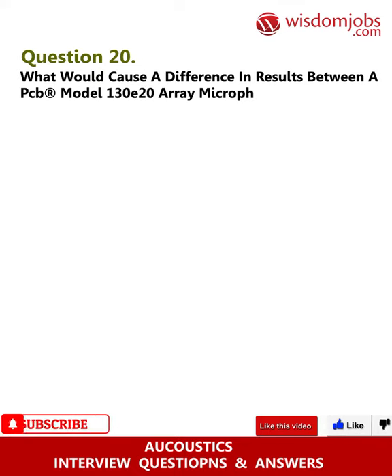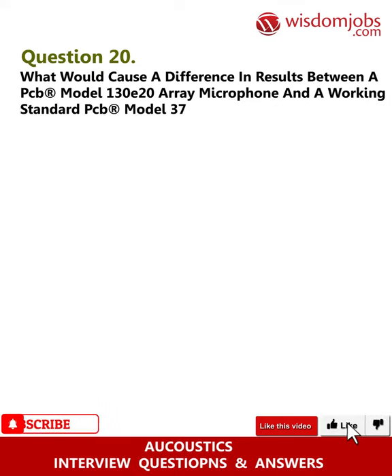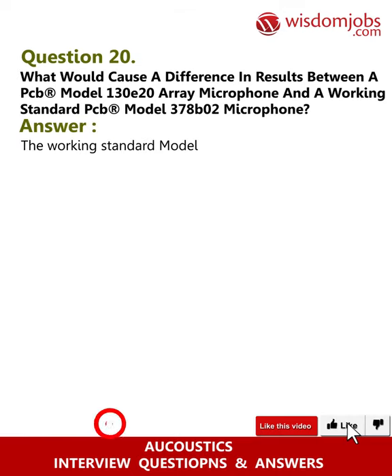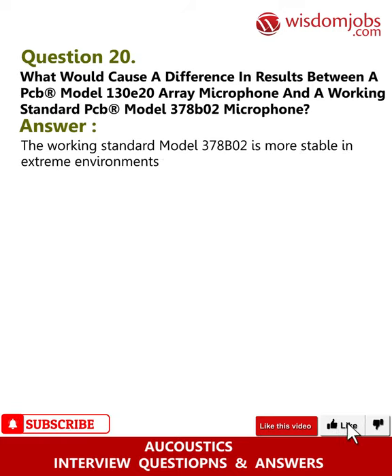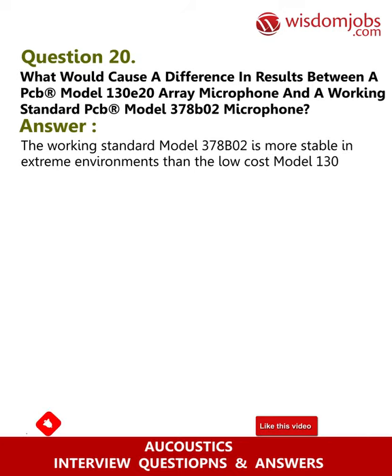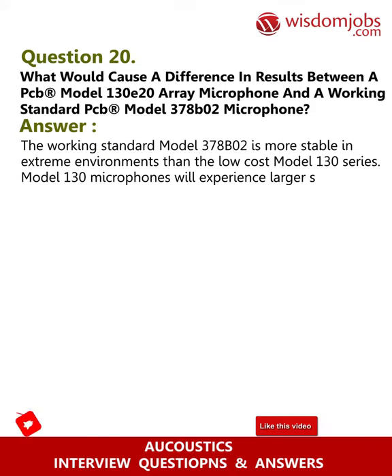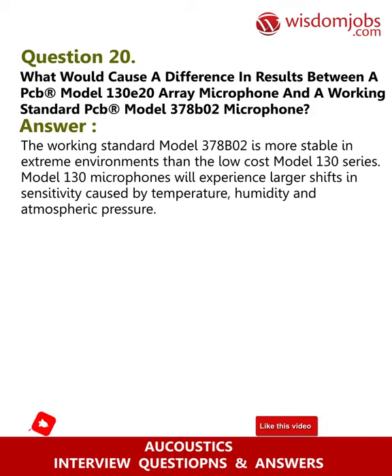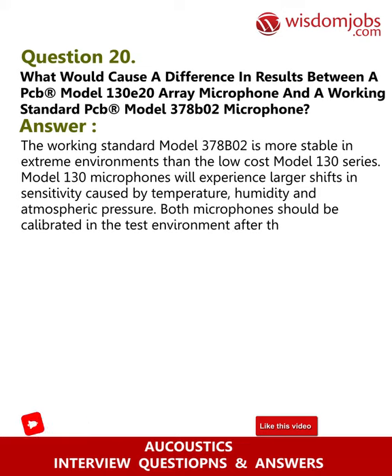Question 20: What would cause a difference in results between a PCB model 130E20 array microphone and a working standard PCB model 378B02 microphone? Answer: The working standard model 378B02 is more stable in extreme environments than the low-cost model 130 series. Model 130 microphones will experience larger shifts in sensitivity caused by temperature, humidity, and atmospheric pressure. Both microphones should be calibrated in the test environment after they have stabilized.